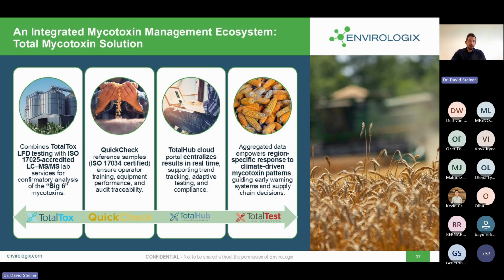The certified QuickCheck reference materials also play a crucial role in this ecosystem. They standardize operator training, but also monitor equipment performance and provide audit traceability, which ensures that both field and lab results are reliable and reproducible. Furthermore, we have centralized data collection through the so-called TotalHub Cloud platform, which allows real-time visualization of trends, adaptive testing schedules, and streamlined compliance management.